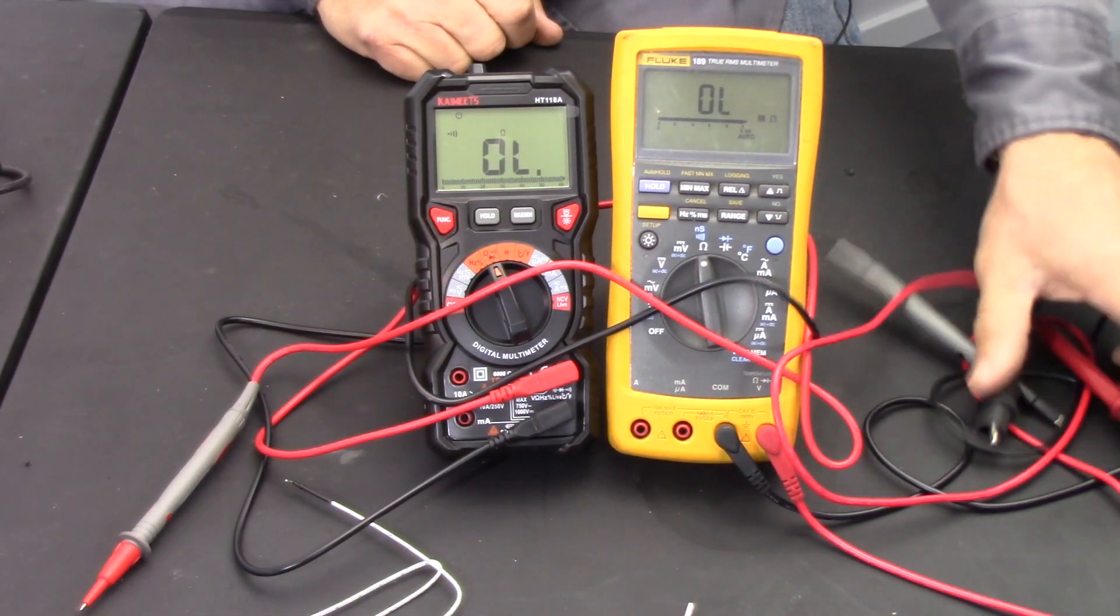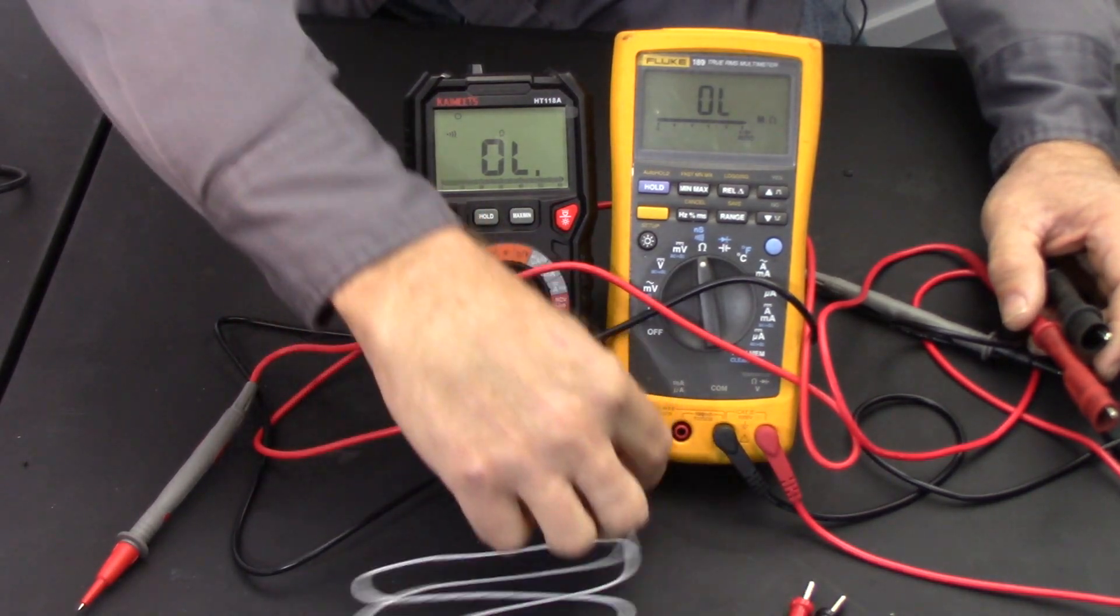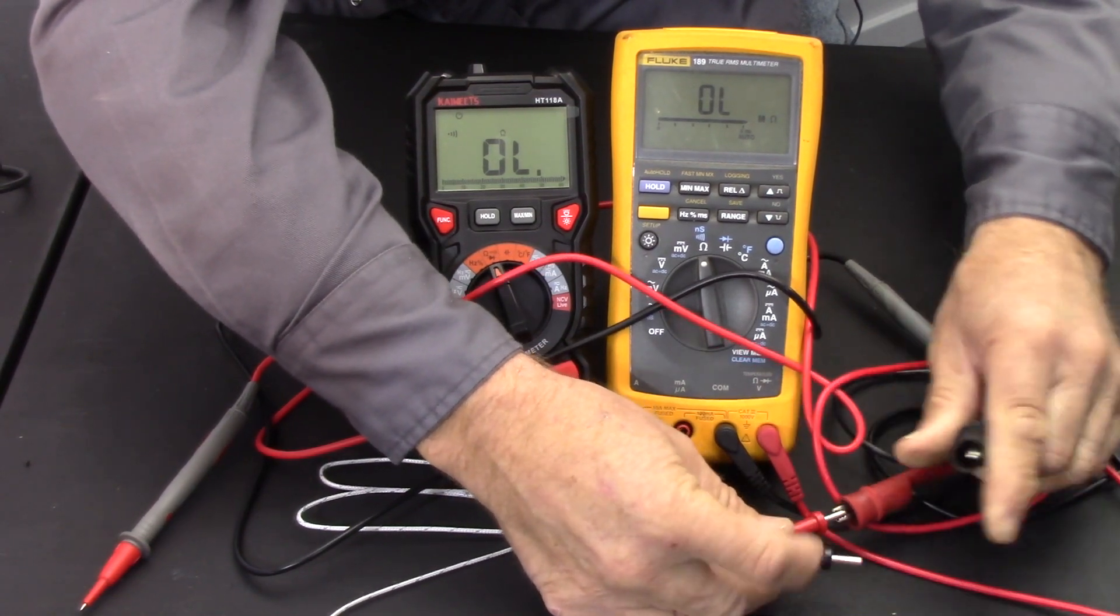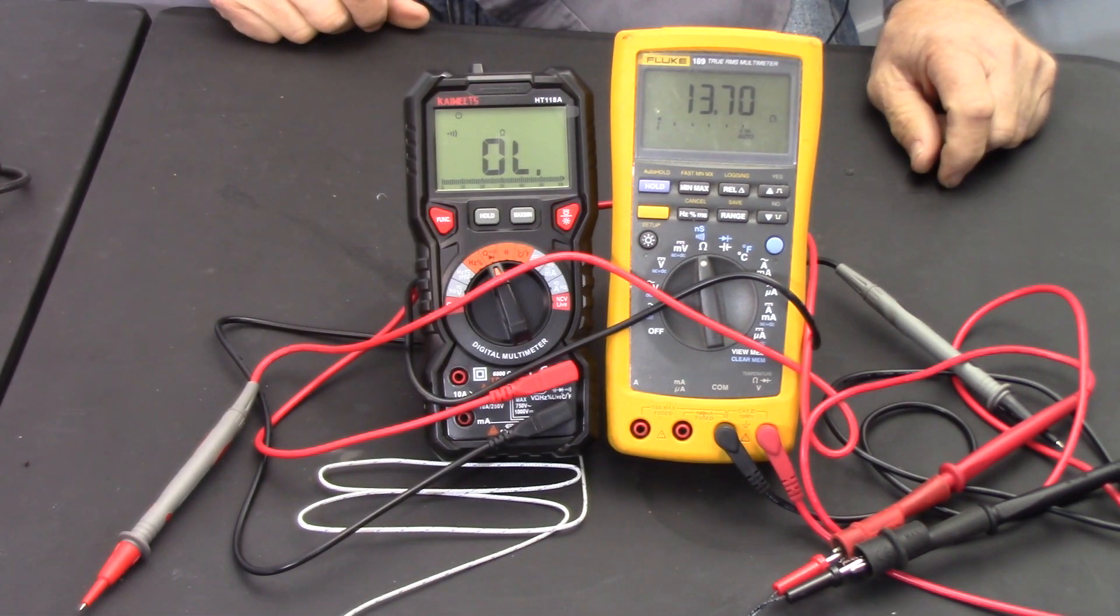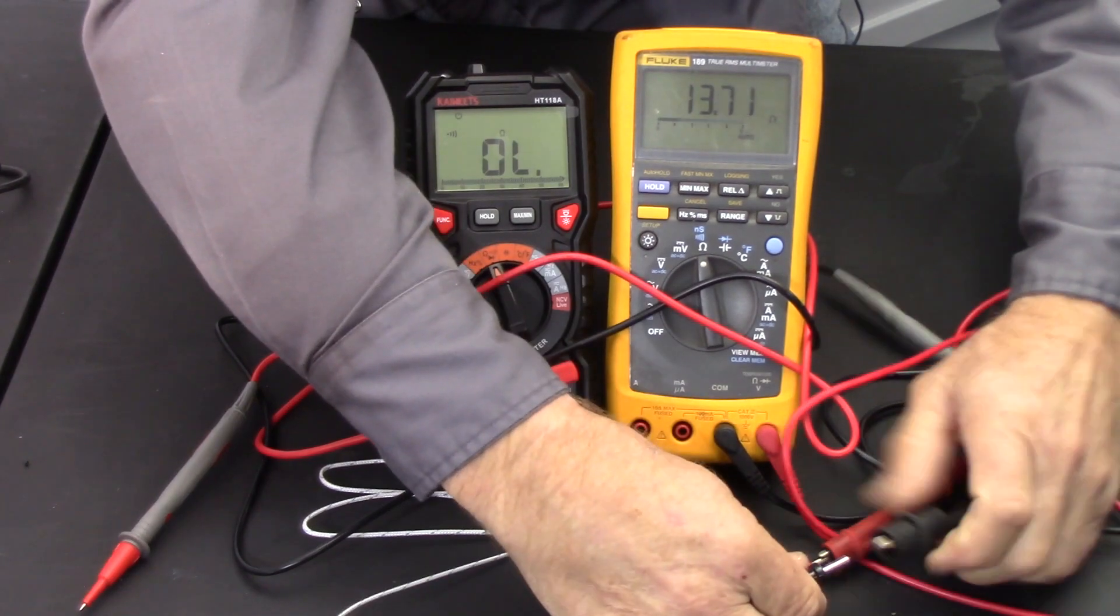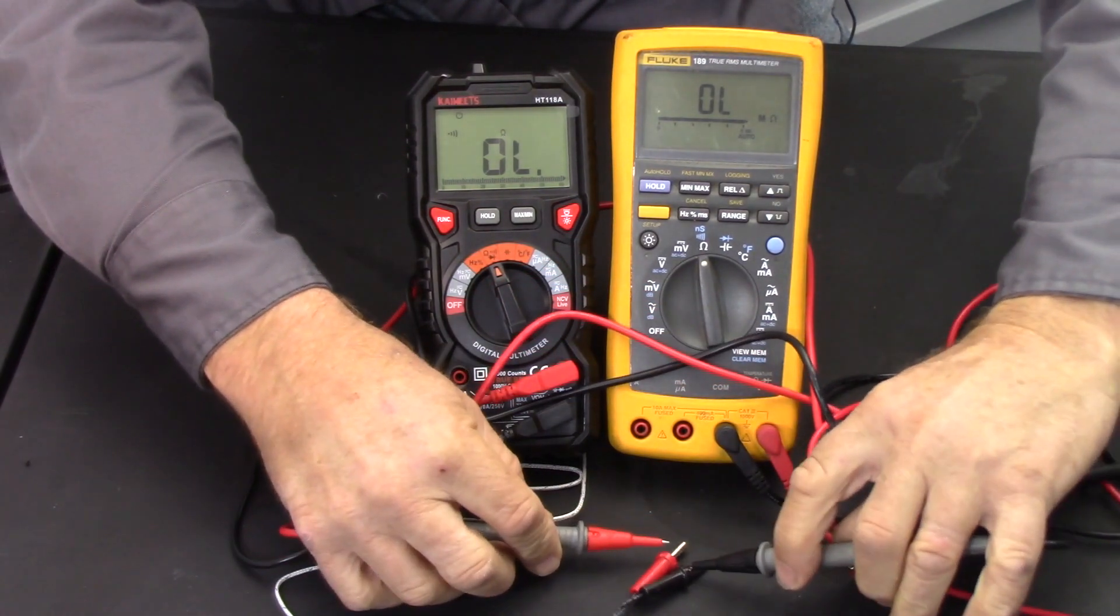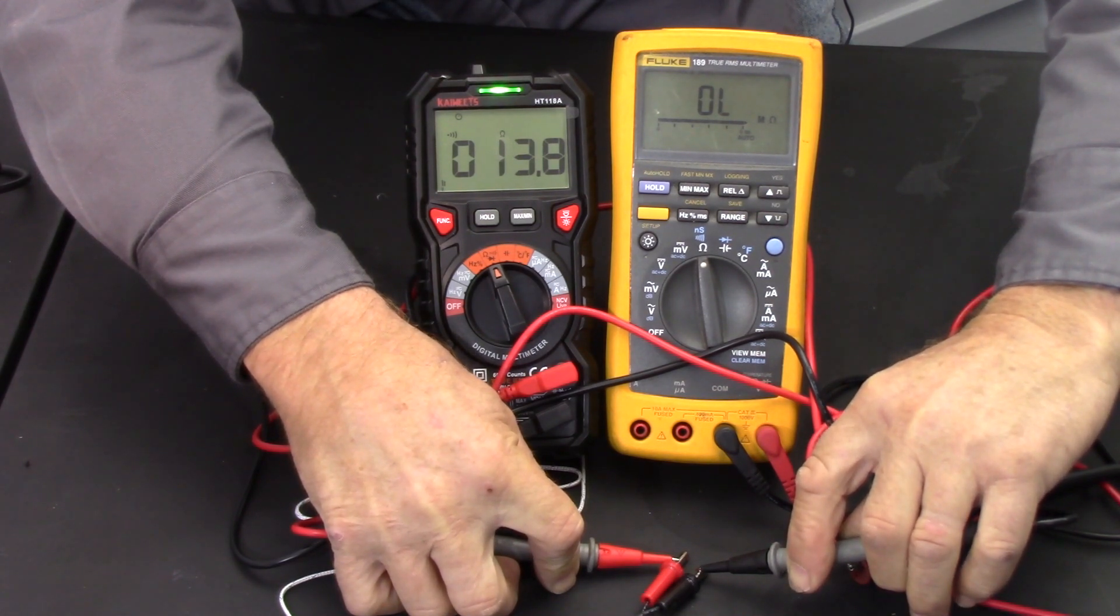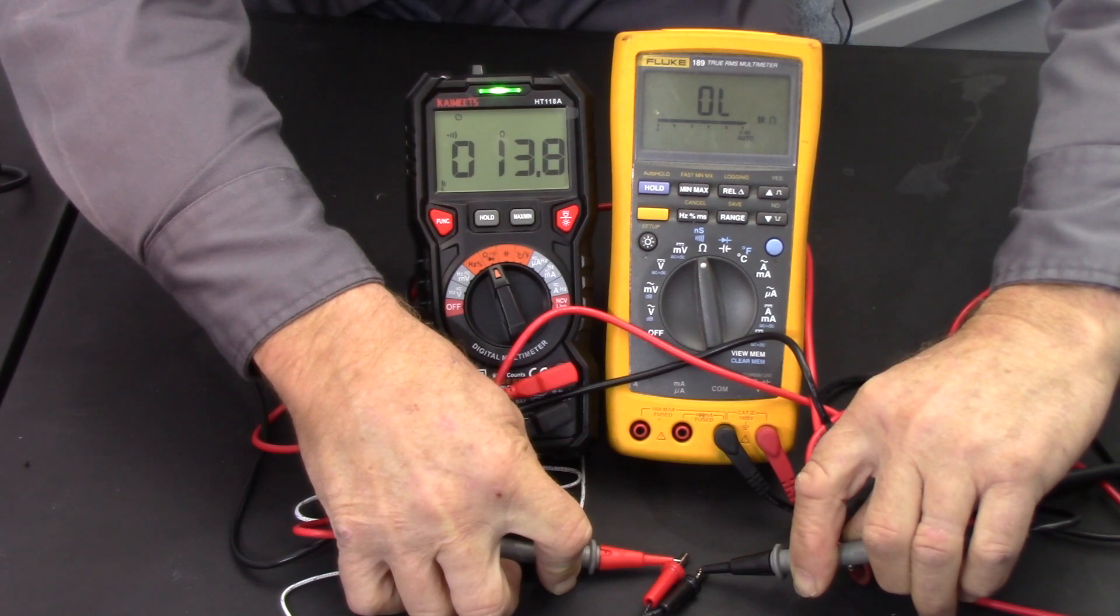Now we'll check the two meters on resistance. What I'm going to use here is the resistive temperature device that came with the Kaiwits meter for measuring temperature. We'll check that with the Fluke, see what the reading is. Setting our meters to the ohms scale. On the Fluke we have 13.7, bouncing around 69, 13.68, right in that range. Now we'll check the Kaiwits. There it levels out to about 13.8, 13.7. Basically again as accurate and comparable to the Fluke 189.